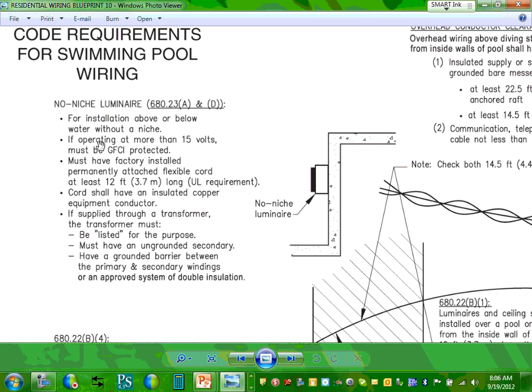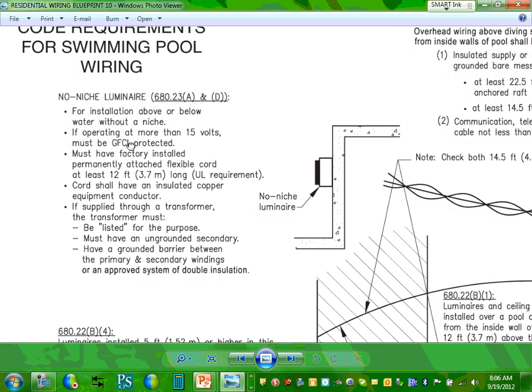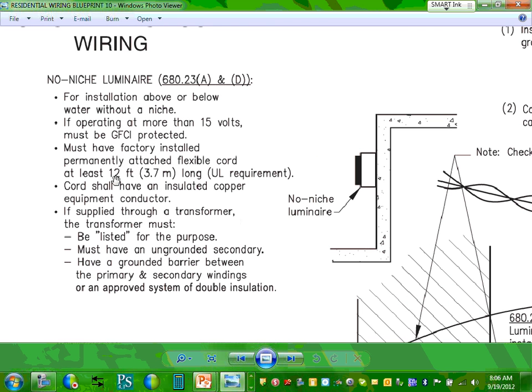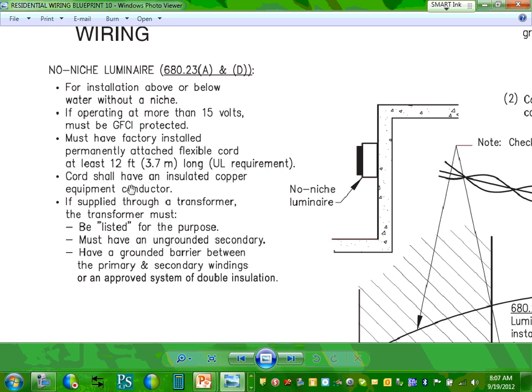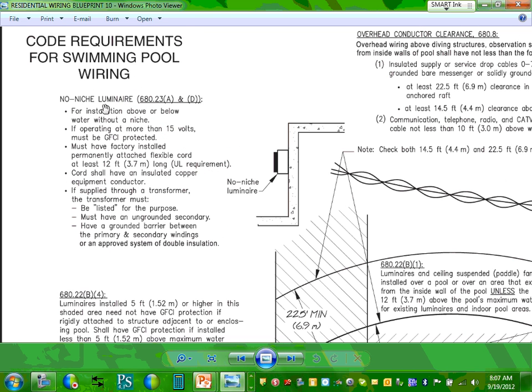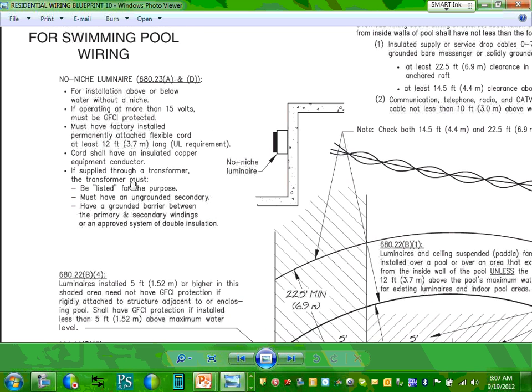Look at this. If operating at more than 15 volt, now they change this 15 volt into low voltage contact limits. You have to put them on a GFCI. So if it's higher than the low voltage contact limit, which is 15 volt, 30 volt, 24 volt or something, you need it to be a GFCI receptacle. Must have factory installation, and they have attached flexible cord with 12 feet because you need to be able to pull them up and maintain them, and it talks about the cord that comes with them. So that's basically the no-niche luminaire requirement.